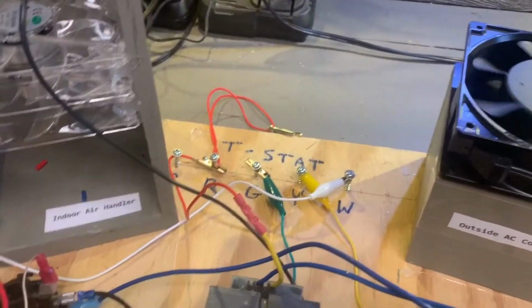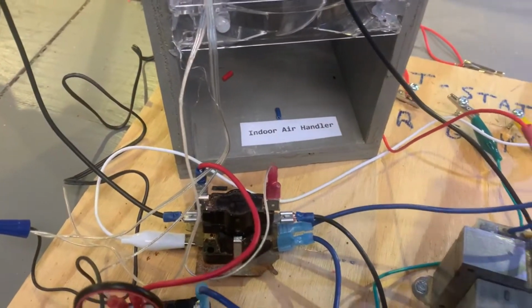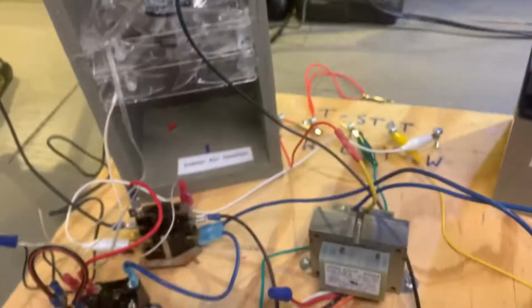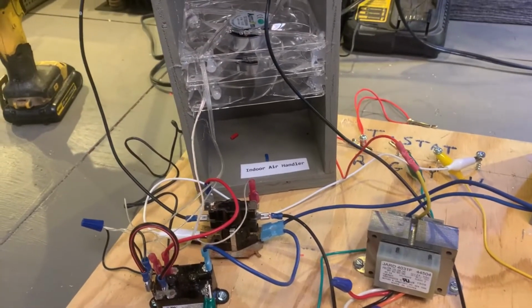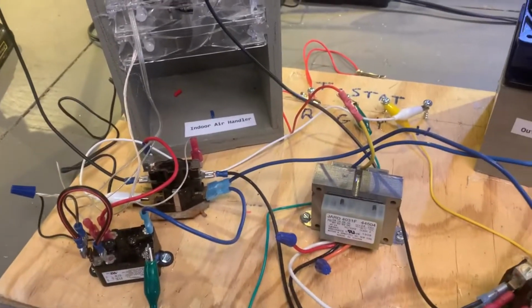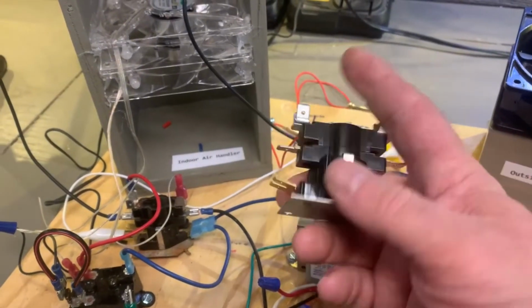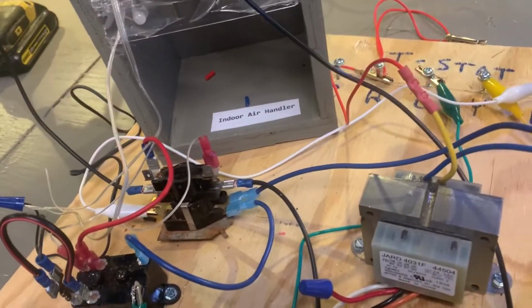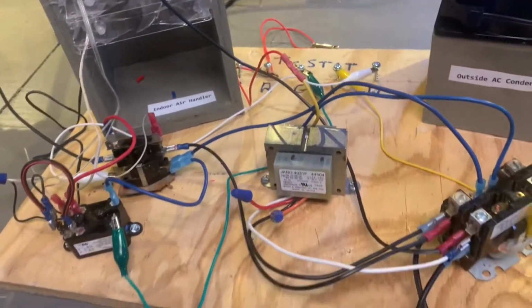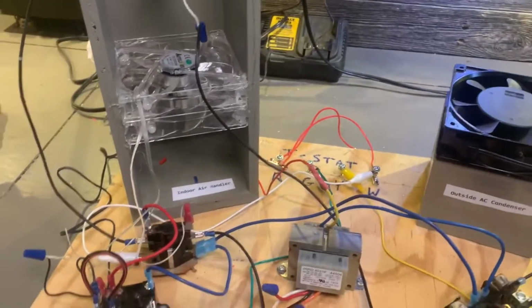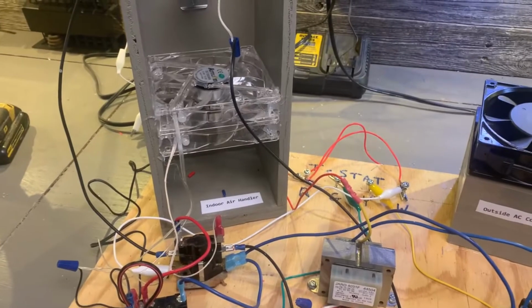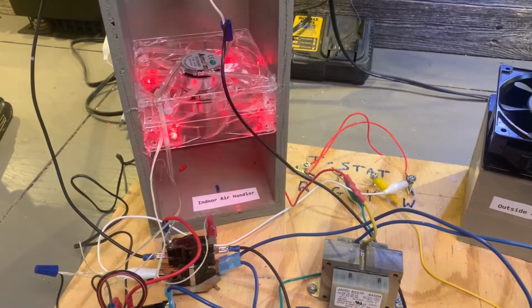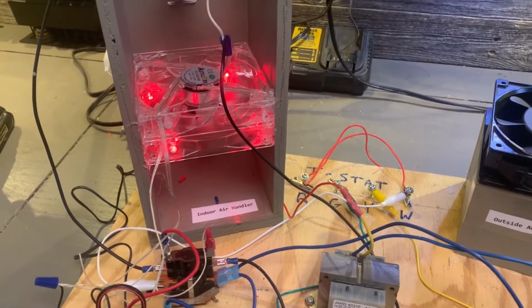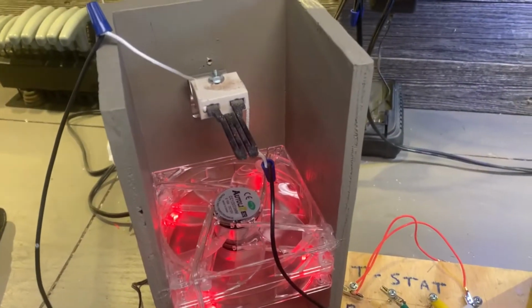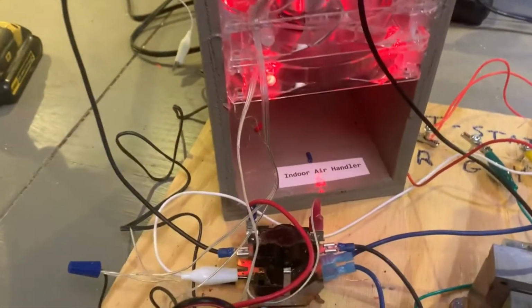The other thing we can bring on here is our heat, which is the sequencer right here. And what's funny, maybe not funny, but while I was doing this project, matter of fact, just a few minutes ago, this sequencer went bad, and I had to dig in a box to get this other one out, but it's going to do the same thing. So the white is our heating jumper, so we're going to go from red to white over here. And the sequencer takes a little bit more time to engage, so we'll just give it a minute here and watch it.